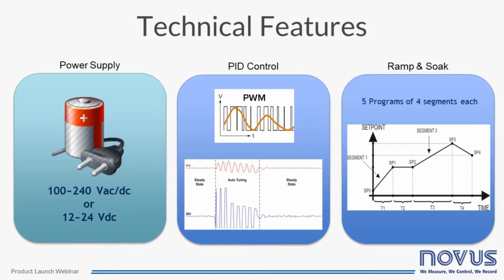The PID constants, the proportional, integral, and derivative, are configurable. However, the N1050 offers automatic tuning of the PID algorithm to facilitate commissioning of the controller on the plant of application. The user starts the auto-tuning procedure, then the controller maps the process and finally defines the new constants automatically, stabilizing the process. The N1050 offers 5 programs of 4 segments each to define recipes of set point profile through ramps and soaks. The programs can be linked, forming a large program with many segments. The time base can be defined as seconds or minutes. This feature is likely used in the food and beverage industry.